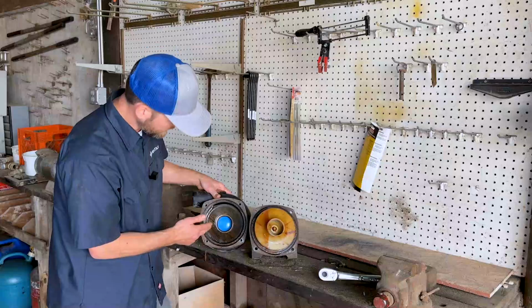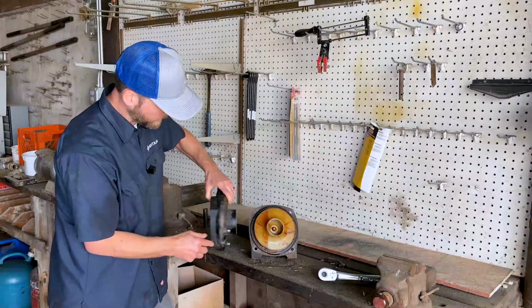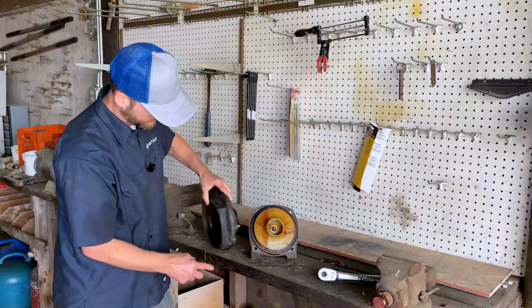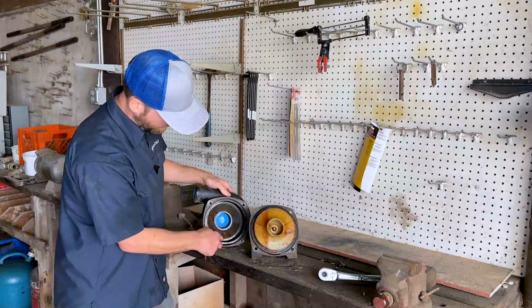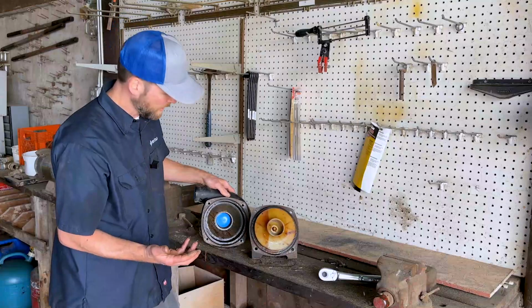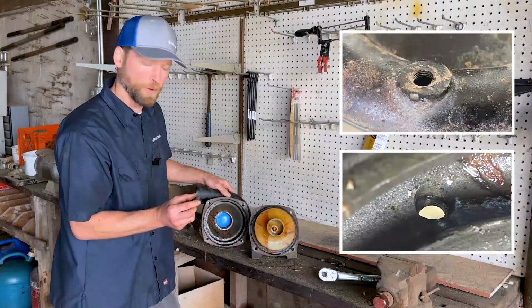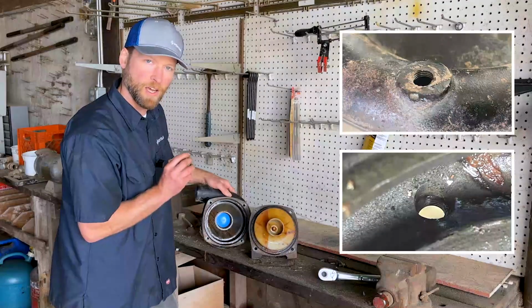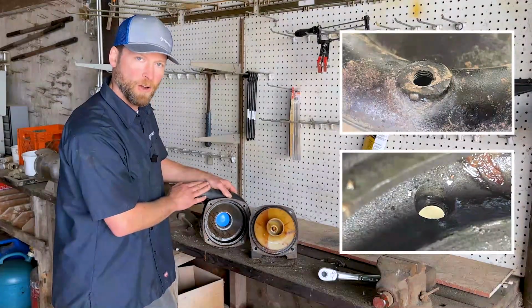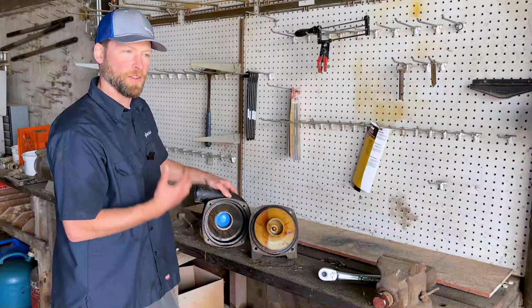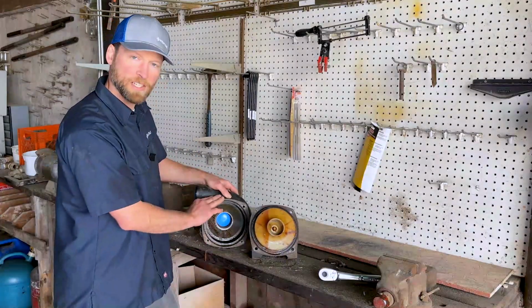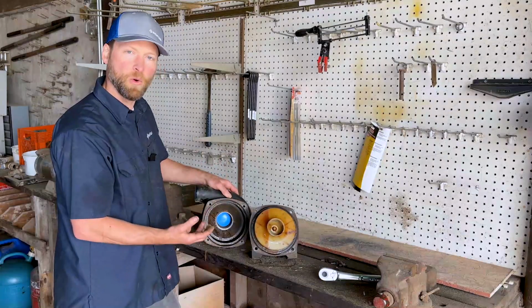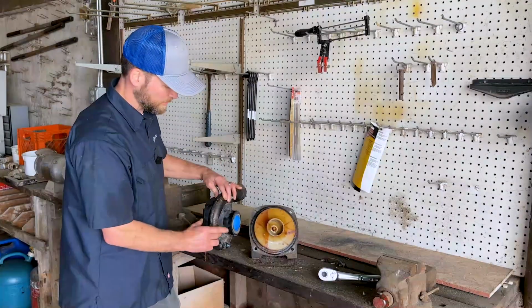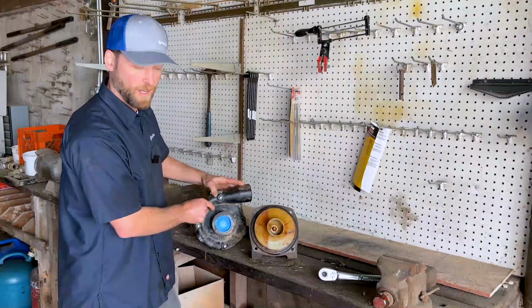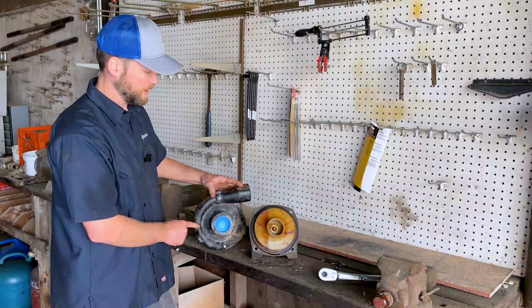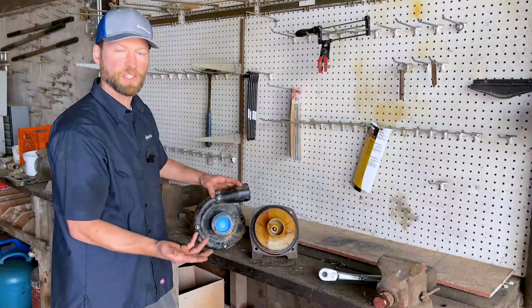One other thing you will notice is that inside there's 4 plugs that are threaded into the casing, and on the inside there's a significant amount of material that has eroded over the years. And so these plugs are barely holding on to the volute. There's maybe 1 or 2 threads that are keeping the plugs inside of this pump volute right now. So that's just something that happens over time. The chemicals you're pumping can be corrosive to that cast iron, and it'll eventually eat away that material, and this could cause a pump leak. So these plugs are barely holding on, and it's good that we replaced the pump when we did, because you'd hate for one of those to come loose this season when you're out in the field spraying.